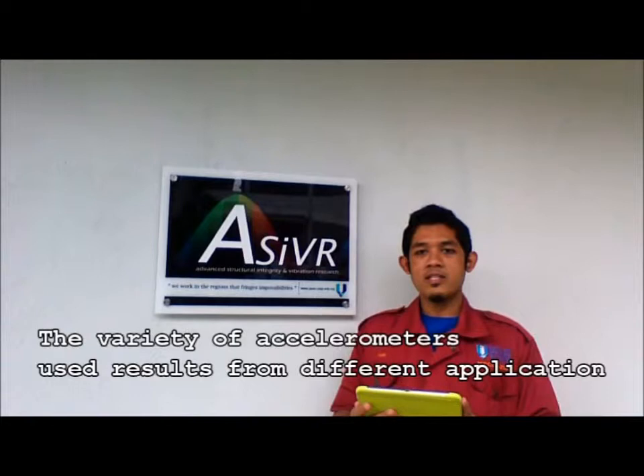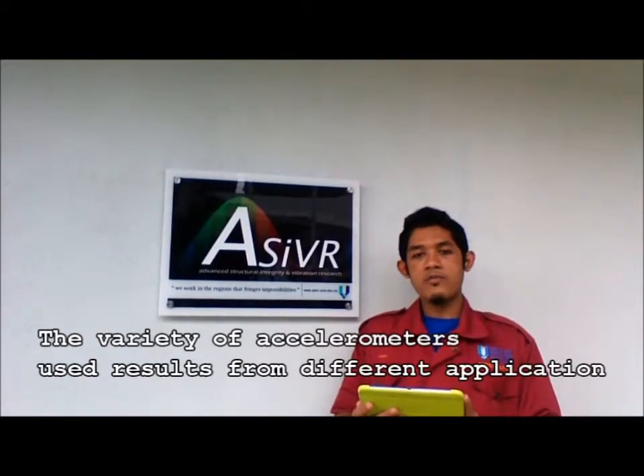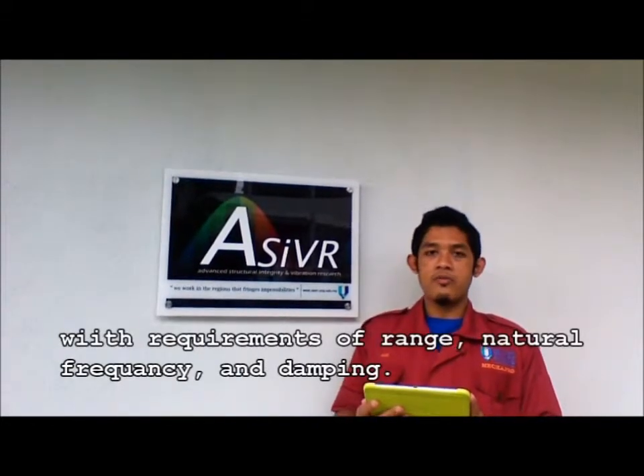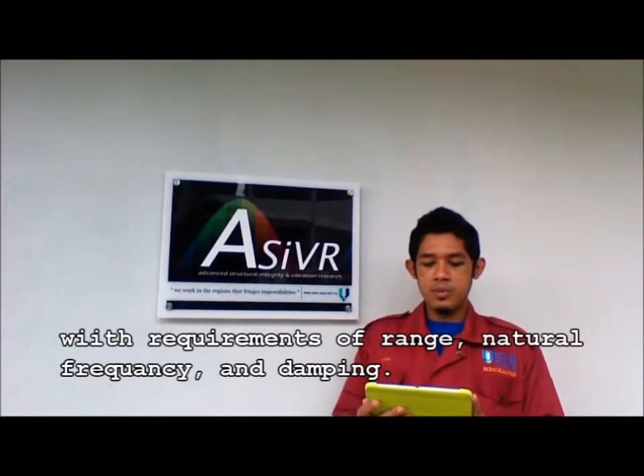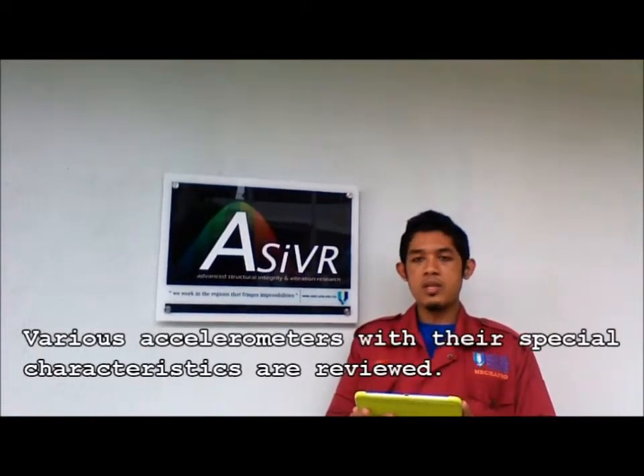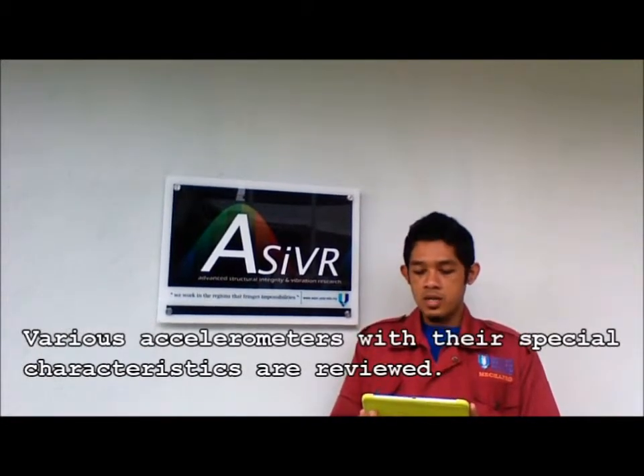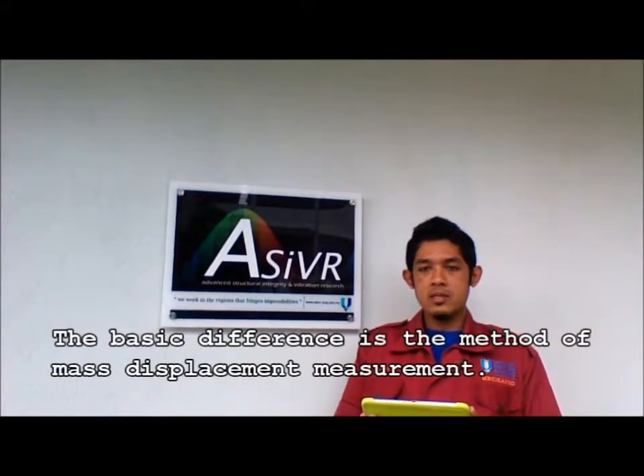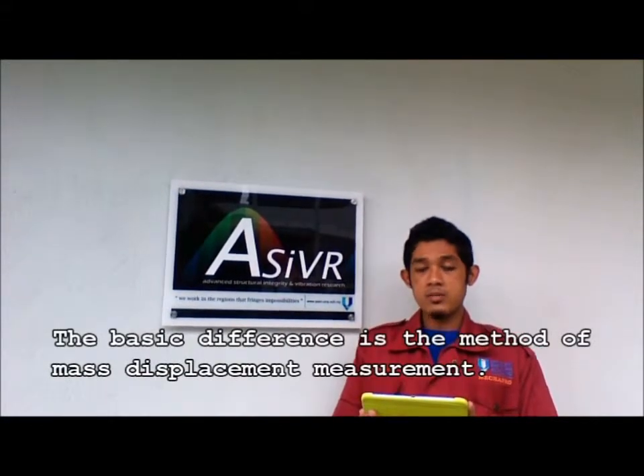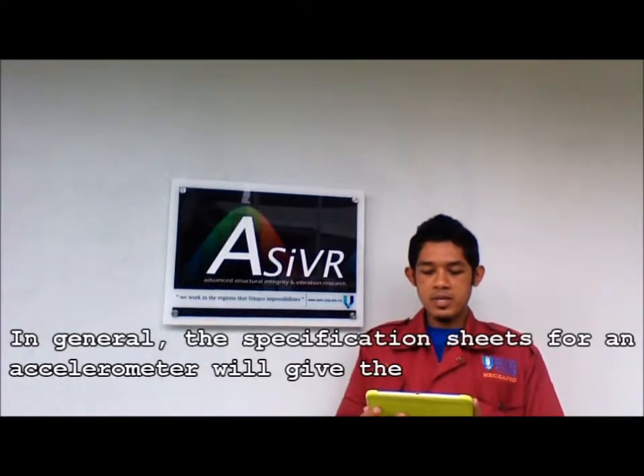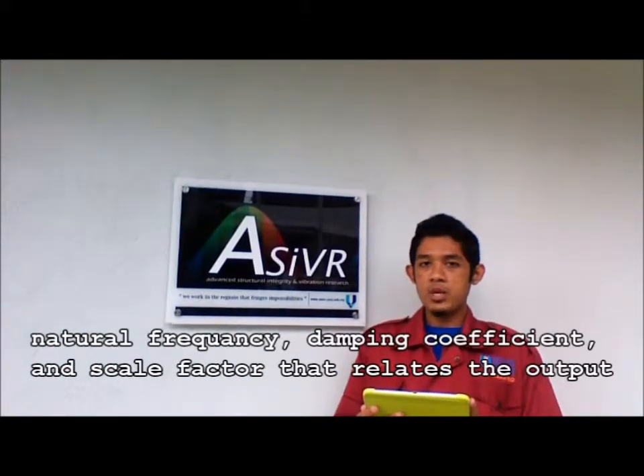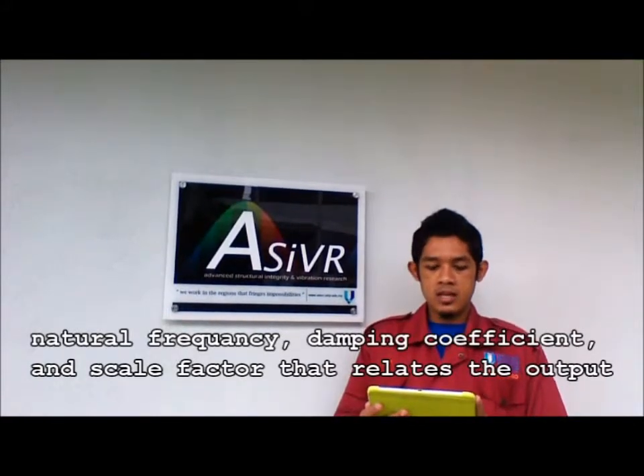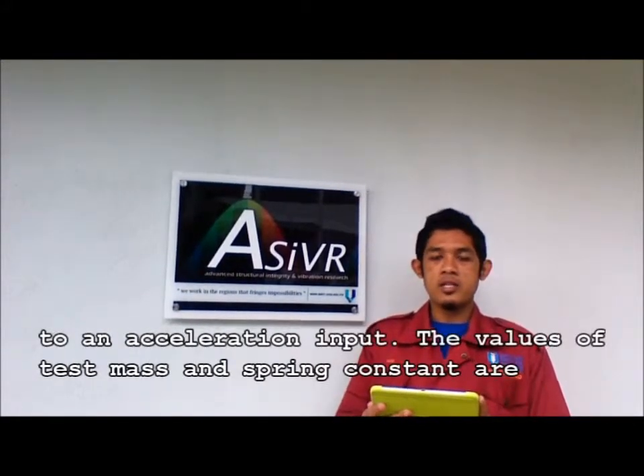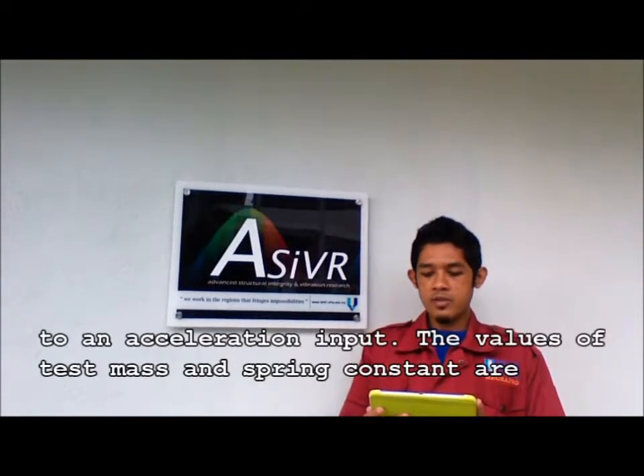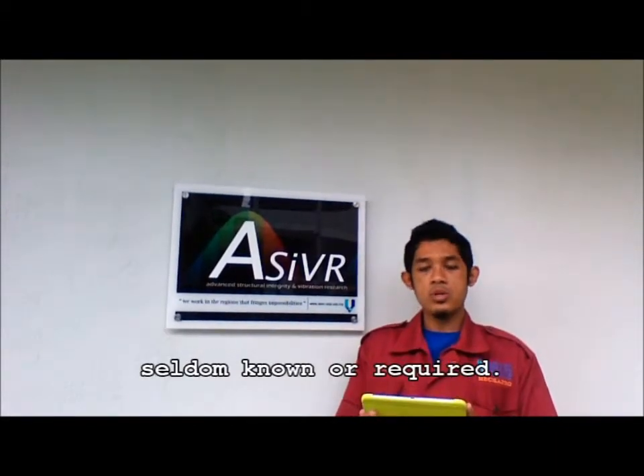The variety of accelerometers used results from different applications with requirements of range, natural frequency, and damping. Various accelerometers with their special characteristics are reviewed. The basic difference is the method of mass displacement measurement. In general, the specification sheet for an accelerometer will give the natural frequency, damping coefficient, and scale factor that relates the output to an acceleration input. The values of mass and spring constant are seldom known or required.